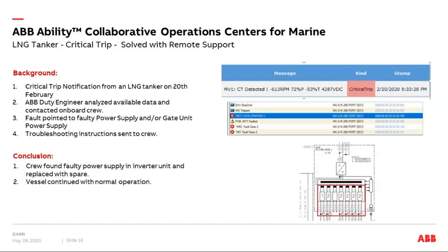At the same time as the SMS or critical trip notification is sent, there is also a batch of data automatically exported from the RDS system on board to the ABB cloud. This contains data typically from 1 hour before the incident up to 10 minutes after it happened, meaning the technical support engineers will almost immediately have access to high resolution data that they can analyze to pinpoint a fault coming in from any of the RDS systems.